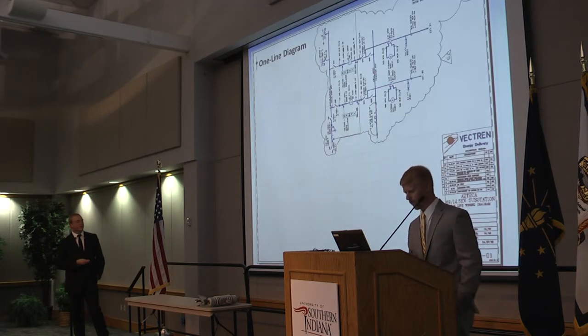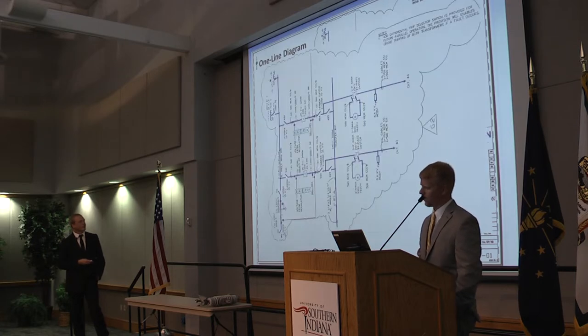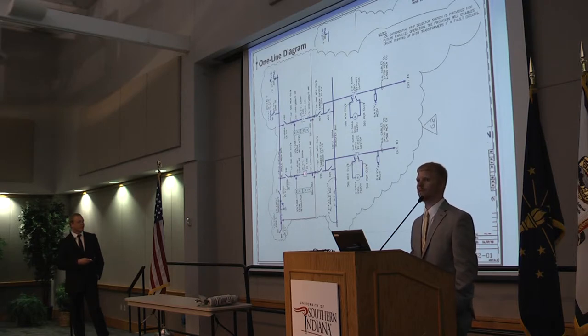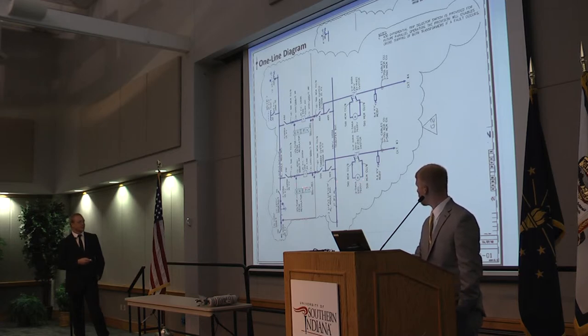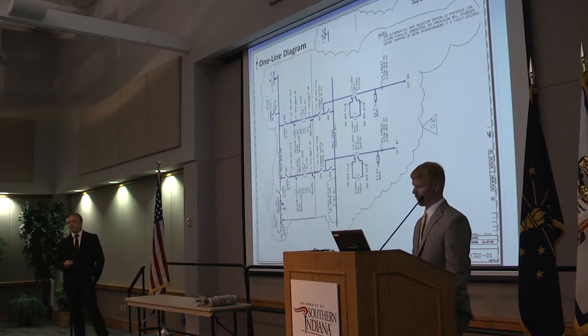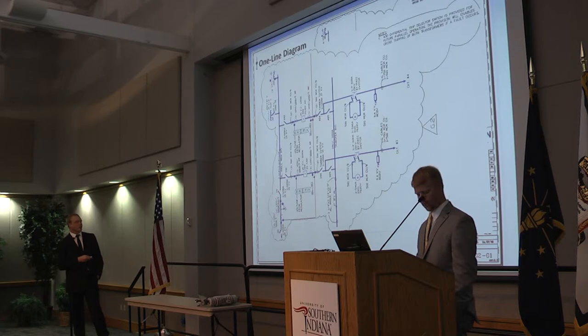This is the one line of the drawing you just saw. If you're looking closely, you can see all the monitoring and all the detail. This is the voltage, or vacuum circuit breaker. These are the voltage regulators, and this is a relay system. Each part you can see has disconnects, so if something were to go wrong, you could go in there and do maintenance on it, and it would also be able to be connected. So if a problem happened here, this breaker would still be connected through this, so we could still operate normally.